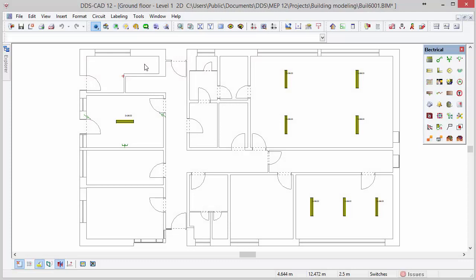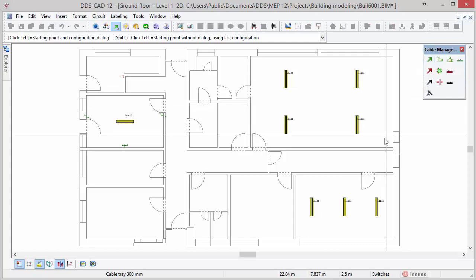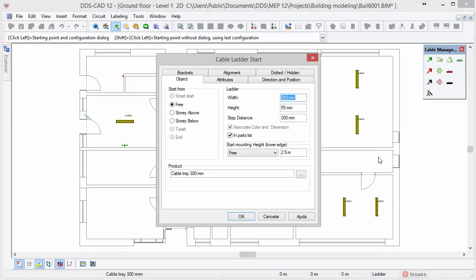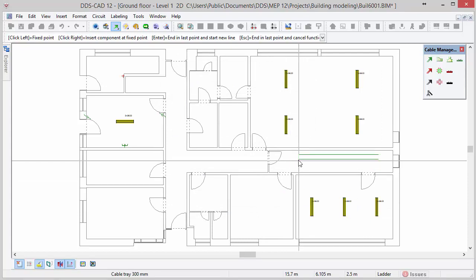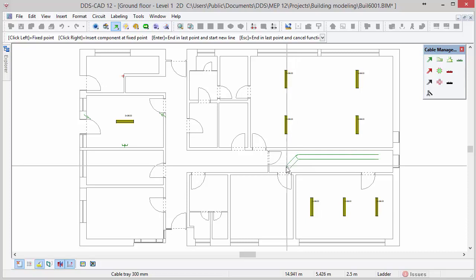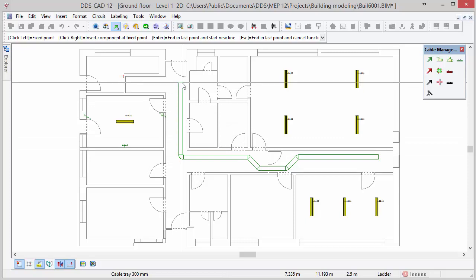Now we will start designing some cable management systems. To do so change the working mode to cable management systems. In the toolbox you will find functions for conduits, cable ducts and cable ladders. Click on the cable ladder function, move the cursor to the right side of the hall and left click to set the start point of the cable ladder. In the dialog you configure start from, width, mounting height and more. After defining the correct settings, click OK. Move the mouse cursor to draw the segment and press left mouse button to change the direction and insert bends. Left click at the endpoint and press escape to close the function.